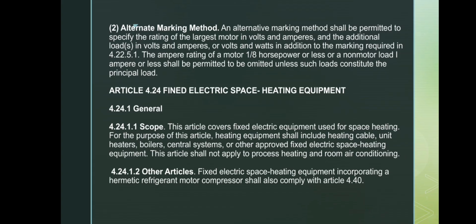Next is the alternative marking method for appliances with motors and other loads. First, the code allows an alternative way of marking. Instead of showing the combined horsepower, the nameplate may list the large motor ratings in volts and amperes and the additional load ratings in volts and amperes or in volts and watts. Very small loads, motors of 1/8 horsepower or less, or non-motor loads of 1 ampere or less, may be left out, unless these small loads are actually the main load of the appliance.